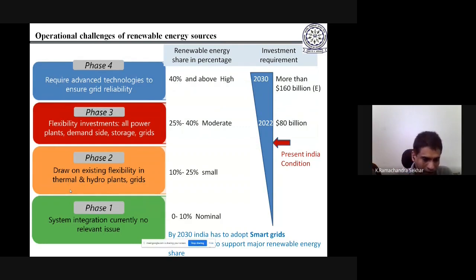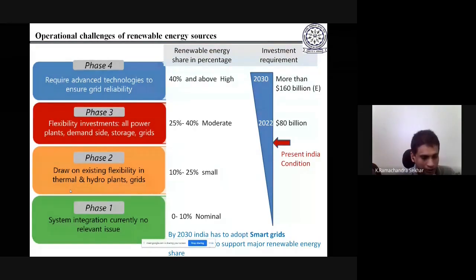With the fall in voltage, other generators come into picture. They try to increase reactive power to boost that voltage, so that the system maintains itself. In that process, even if all our renewable energy sources act, it creates a huge oscillation, which creates instability in the power system, and the complete network can collapse. So inertia is important for any network.